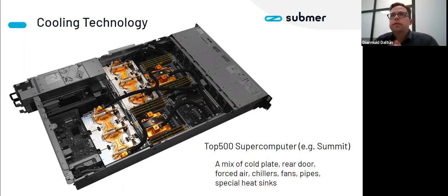On one end we have what can be seen here, the direct liquid cooling, direct to the chip cooling, with the pipe work that represents it. In this node there are probably about 20 different liquid pipe connections, and across the whole of Summit there are more than 100,000 pipe connections, something to consider, since each of those connections is a risk.